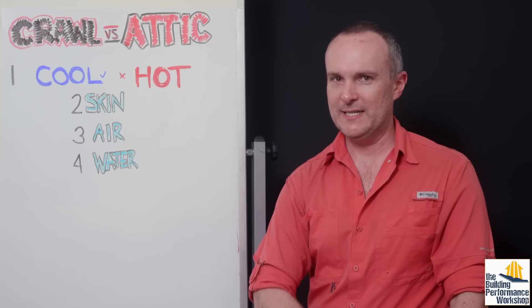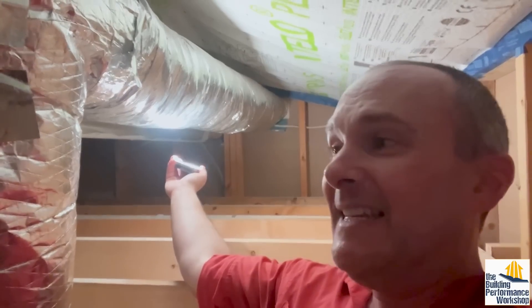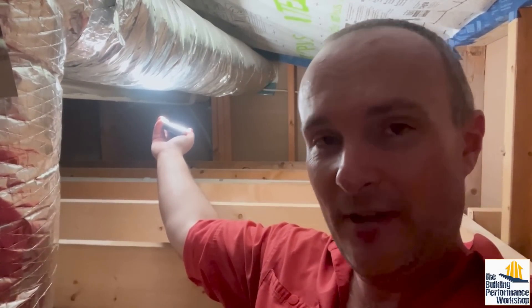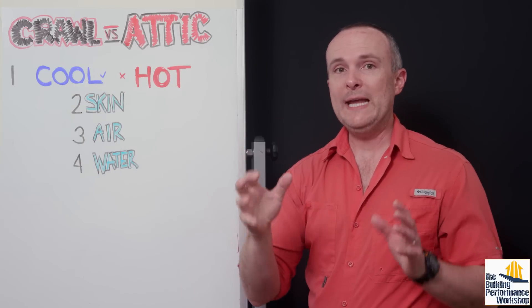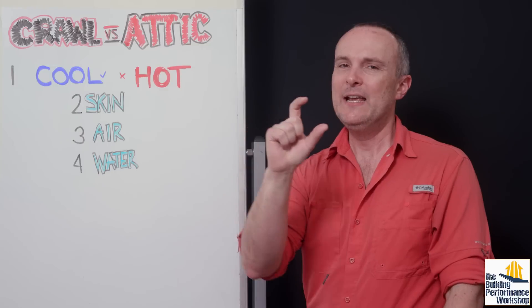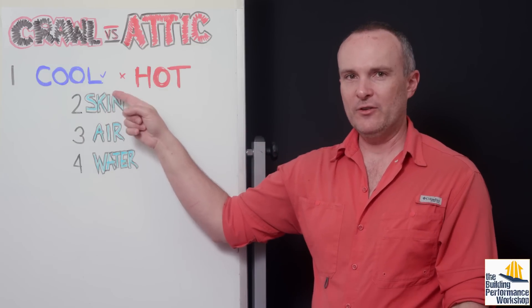This is my conditioned attic. It looks like it's part of the enclosure, and it's not just looks — it actually acts like it is the same exact temperature and humidity up here as it is down in the crawl space and the rest of the living space in this house. We like cool because if we're trying to contain something that's conditioning our home — HVAC equipment, heating, cooling, ventilation — cool is better because the delta T, which is the temperature differential, is going to be much slimmer in the crawl space than in the attic.